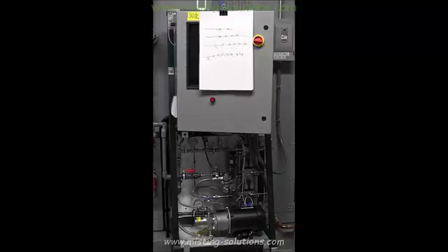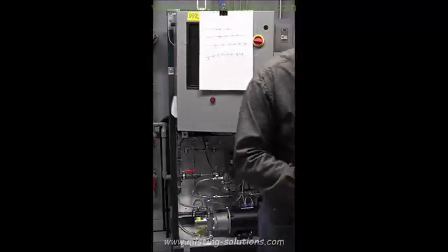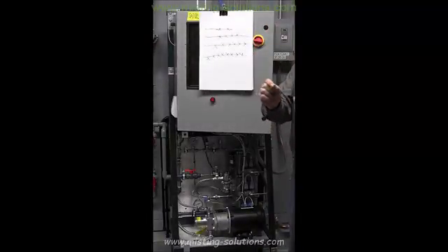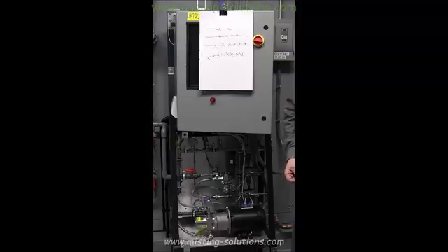Here's 4 or 5 nozzles up here, for example, and each one of them has a little ball valve with a spring check in it, and then it's got a little orifice or a little pin in it to kind of swirl the water around as it comes in. And then here's the nozzle and its tip. So that goes in there, and there's spring pressure on it when you put it back together. And there's different size springs. This one happens to be, and most of them are, around 300 psi. So if you didn't dump it, it would still have 300 psi on it. Yep.